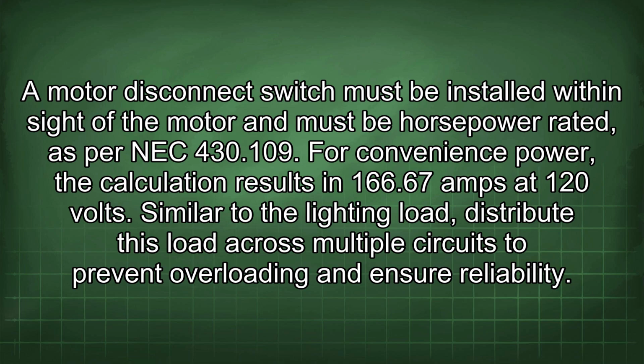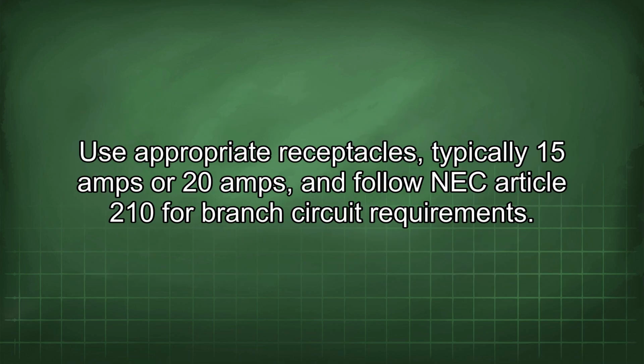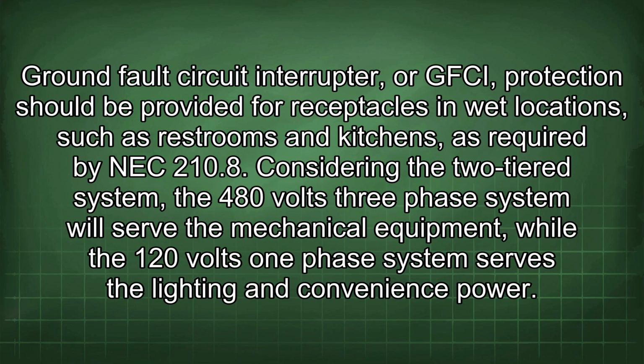166.67 amps at 120 volts. Similar to the lighting load, distribute this load across multiple circuits to prevent overloading and ensure reliability. Use appropriate receptacles, typically 15 amps or 20 amps, and follow NEC Article 210 for branch circuit requirements. Ground fault circuit interrupter, or GFCI, protection should be provided for receptacles in wet locations, such as restrooms and kitchens, as required by NEC 210.8.